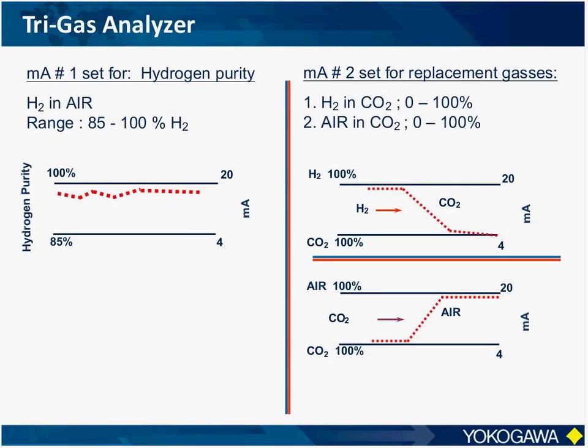Now, this illustrates what the output of a vibrating element system typically looks like in these types of applications. One 4 to 20 milliamp output represents the percent concentration of hydrogen in air. The second output represents the concentration of hydrogen in carbon dioxide or the concentration of air in carbon dioxide, depending on which purge cycle is being performed. Now, this setup allows one vibrating element system to act as a tri-gas analyzer, where all three situations can be monitored by one system.